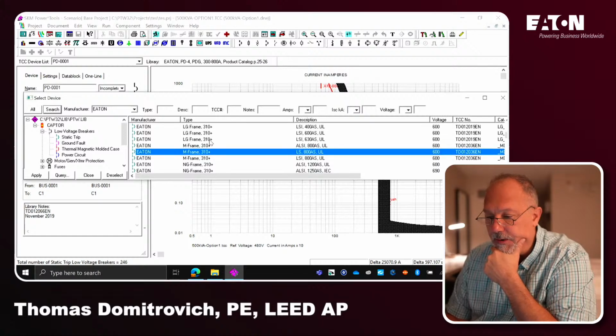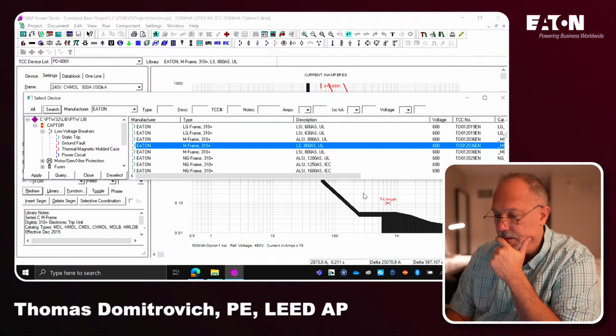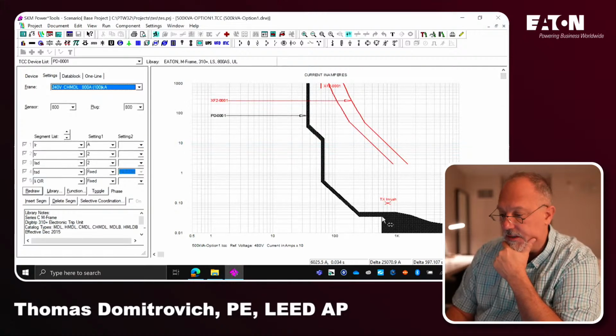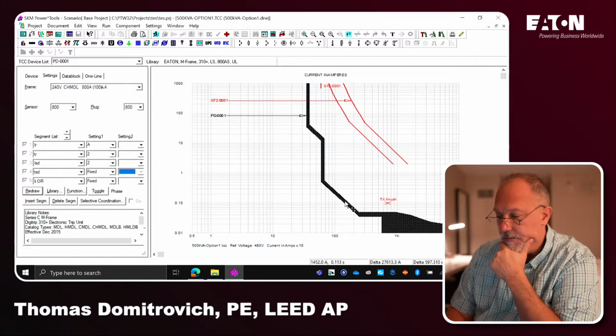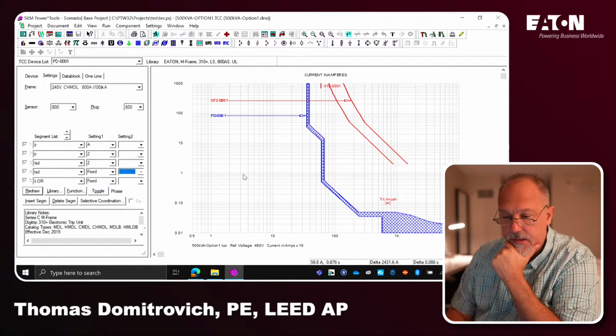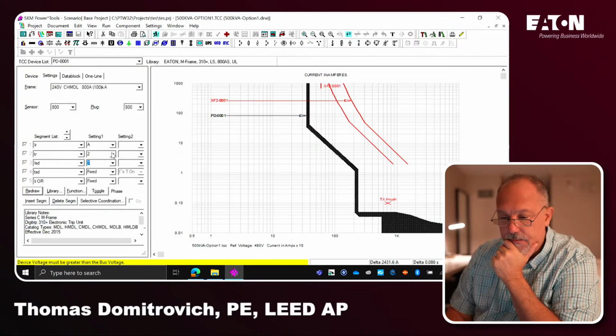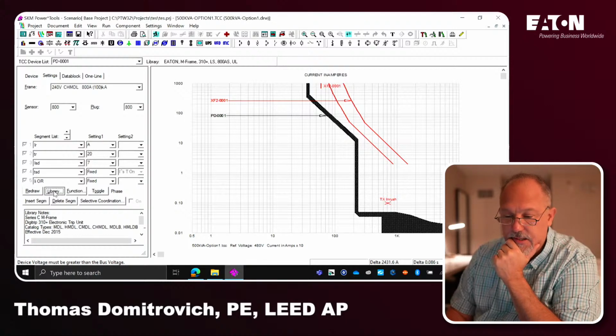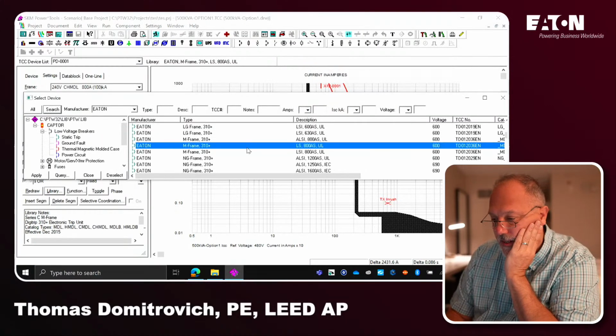It's an M frame. Can't get an L frame, so let's do an M frame. Woo doggy. So this curve here looks crazy, doesn't it? Instantaneous is fixed. Short time delay, I'm going to turn that all the way up to 7. Turn that all the way up to 20. I'm at 800, so I can't get that. This is a primary breaker, so I need to fix that.